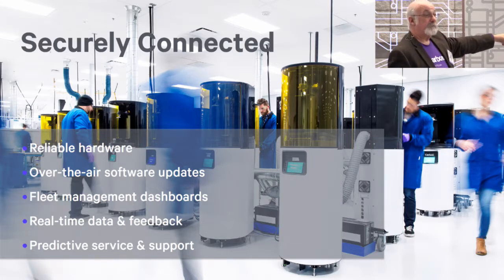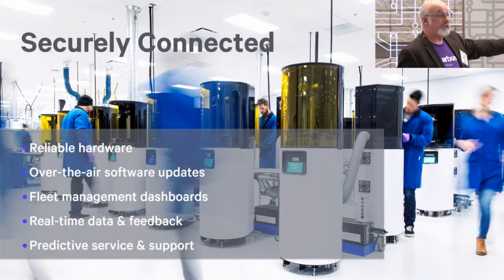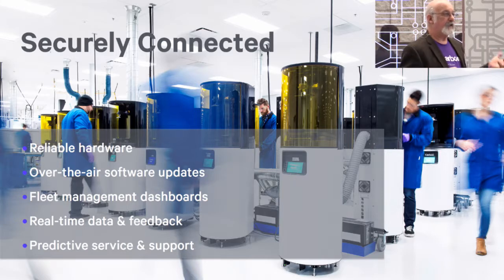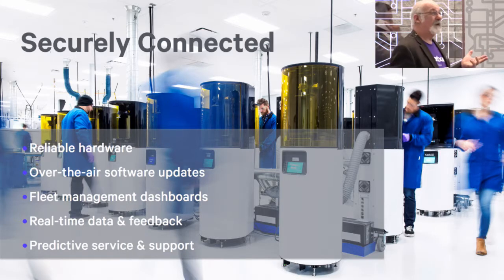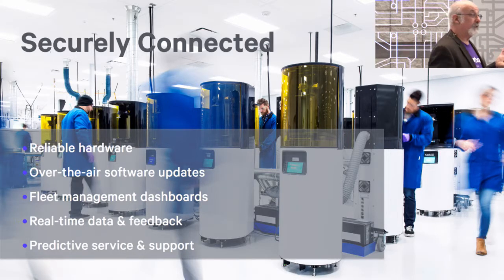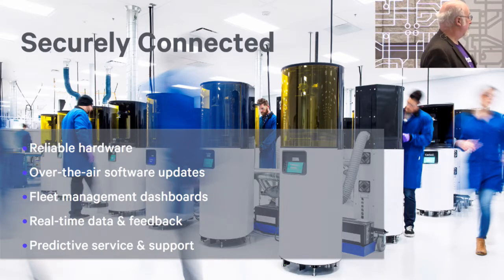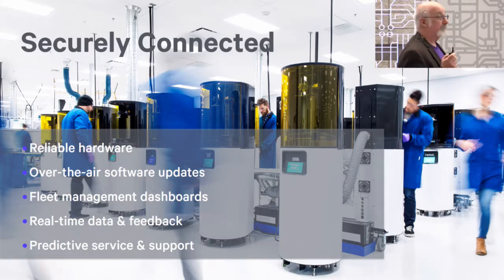We have real-time feedback on the machine's health and its operating characteristics, and we're monitoring that continuously back at Redwood City. We see before you do that there's a problem with the machine that you may never get to see because we'll have compensated for droop in the light engine. Or we'll be ordering that part that you need delivered and have it to you the next day. In a healthcare setting, waiting a week may not be appropriate. And we feel that that's something that we bring to the table, this real-time support and active prediction of machine's operation.